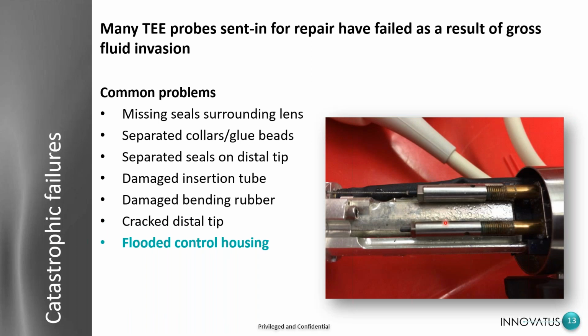And then a flooded control housing. We actually get probes in where somebody who may not have been trained properly in SPD or some other area where the probes are being disinfected may actually immerse the control housing of the probe within the disinfectant solution or the enzymatic solution. There are no probes out there where it is okay to immerse the control housing.